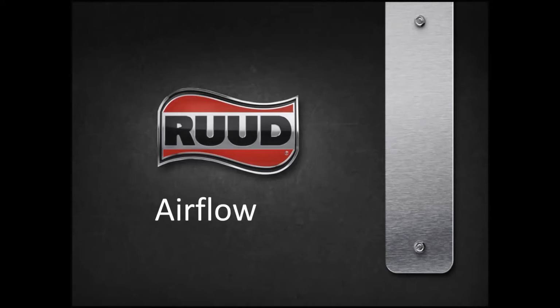So, airflow. I've said this a lot. If you've been in any of my classes, you probably heard me say that airflow is the most important thing that gets looked at last when somebody has a problem with a piece of equipment. Typically, when someone goes out to do a startup, or a service call or maintenance, they hook their gauges up, look at their pressures, and look at the charging chart to see if the charge is right, without ever really verifying or checking airflow.